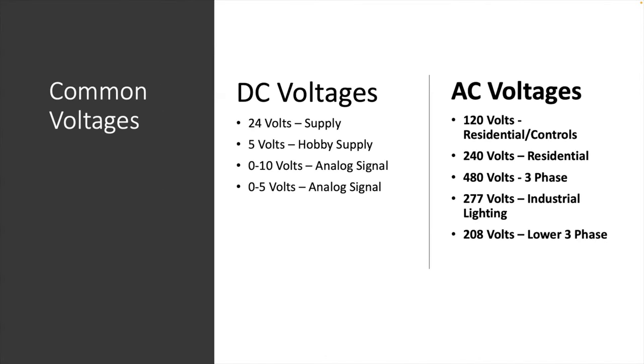Some of the common DC voltages that we will see in industry are 24 volts, which is generally the motor controls supply. 5 volts, which I put as a hobby supply because things like Arduino run off 5 volts. There's also a 0 to 10 volt analog signal and a 0 to 5 volt analog signal. And there's another form of 24 volts that is actually a current signal called 4 to 20 milliamps, but it runs on 24 volts.